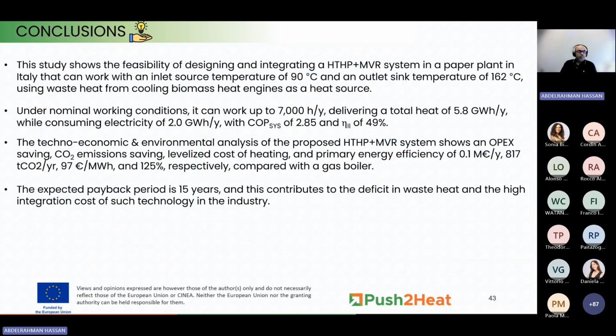And finally, as a conclusion, this study shows the feasibility of designing and integrating a high-temperature heat pump plus mechanical vapor compression system in a paper plant that could work between 90 degrees as a source and sink up to 162 degrees. Under nominal working conditions, it can work up to 7,000 hours, delivering total heat of 5.8 gigawatt hour per year, consuming 2 gigawatt hour per year of electricity with a COP of the system of 2.85. And I don't know why it's like this, but this should be a second law efficiency of 49%.